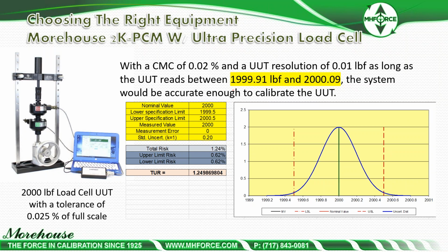I have a CMC of 0.02, and what I'm looking at here is 1999.91 and 2000.09. So I have very little room. If you look at this graph, I have to have an almost perfect measured value in here. I'm in that car door scenario where I need to shimmy out of my car door. I cannot open the door, so I really need to be careful with my measured value. That location of the measurement needs to be almost perfect in this scenario, or I'm not going to be able to make that statement of compliance.